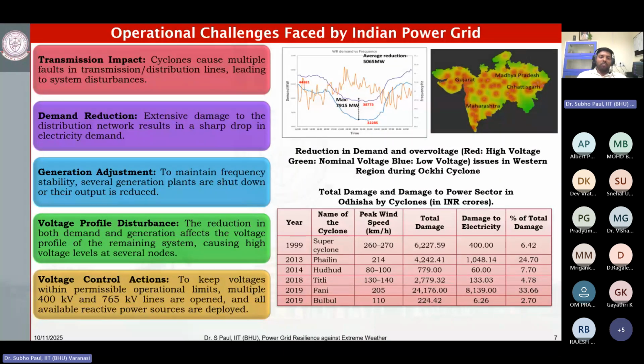There is a huge sudden reduction in demand, and that sharp drop cannot easily be mitigated by the generators, since they cannot cope up with this drop by reducing their inertia. It takes some time, because of the mechanical time constant, to reduce generation, and during that period you see an increase in frequency - because inertia is very high but load is very low and generation is very high, you get a higher frequency as well as an overvoltage problem.